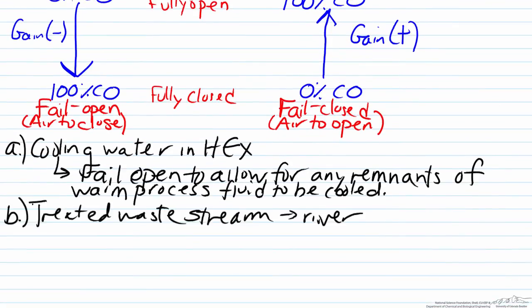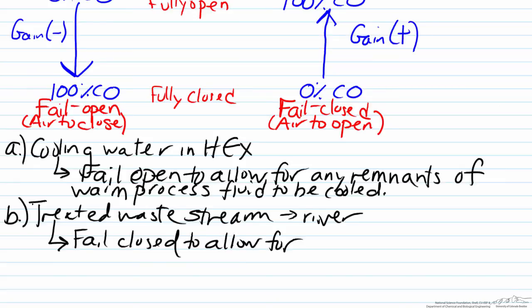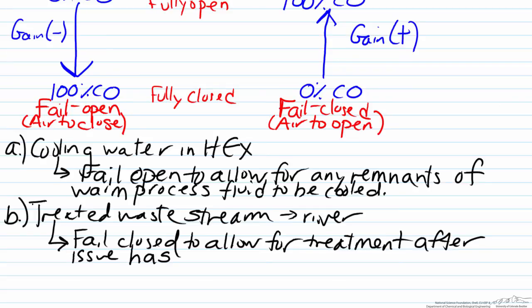Part B: the concern here is that if the process underwent a power outage, fluid would no longer be treated as desired. This could result in releasing fluid that is off specification and potentially quite toxic to the environment. Therefore we would want this valve to fail closed, to allow for treatment once whatever issue caused the power outage has been remediated.